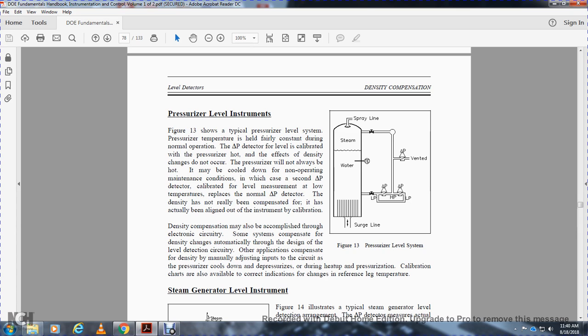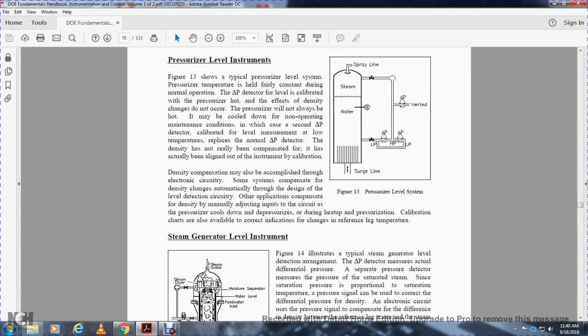Density compensation may also be accomplished through an electronic circuit. Some systems compensate for the density automatically through the design of the level detection circuit. Other applications compensate for the density by manually adjusting the input to the circuit. As the pressurizer cools down and depressurizes during heat up, a calibration chart is available to give the correct indication with the reference leg temperature.